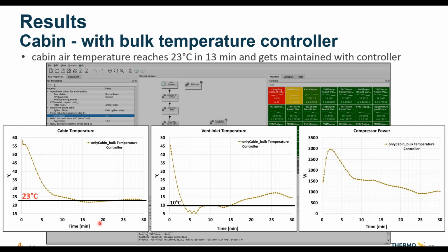So similarly, I have the three plots. The cabin air temperature starts very hot, and here I have marked the 23 degrees Celsius reference. Here you see the 23 degrees C is reached in 13 minutes, and it gets maintained around that temperature. That's because when you look at the vent inlet temperature, we set the target of 10, which is reached also similarly around 7 minutes and maintained for a while. Later, as the cabin temperature drops below 23, the vent inlet temperature tries to adjust by increasing, and then the cabin temperature is maintained around 23 degrees C.